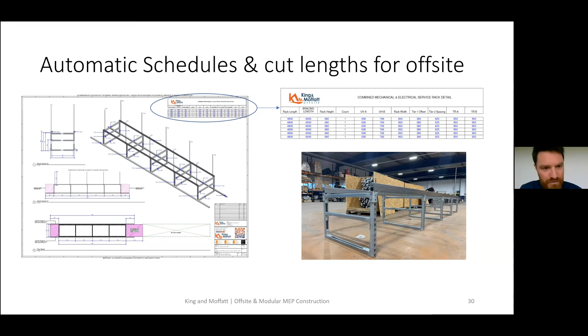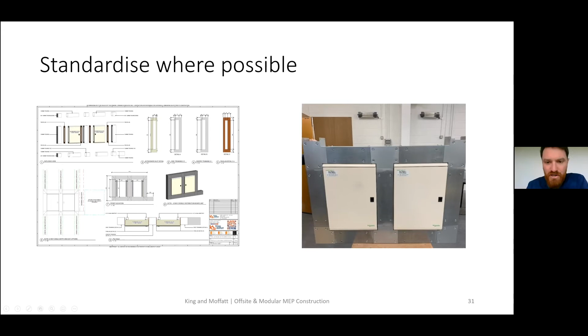This one we talked quickly about, there was a photo of it in an earlier slide. There are 2 distribution boards, and it mightn't look like it from the photo, but that trunking, that containment wrapped around the distribution boards, is extremely time-consuming work to do on site. There are slots taken out of that trunking on the inside to allow cables in and out, and it's put on a full frame that can be hung up and mounted onto a wall on site. You'll see on the left-hand side those uni struts to hold it inside. But another thing that can happen is these 90-degree accessories - they're not the off-the-shelf accessories, and the ones that typically arrive on site have a chamfer on them, which means it can't sit tight around the distribution boards, and it can look very messy and impact your program on site when the wrong stuff starts coming to site. So you're removing the risk and keeping the quality very high.